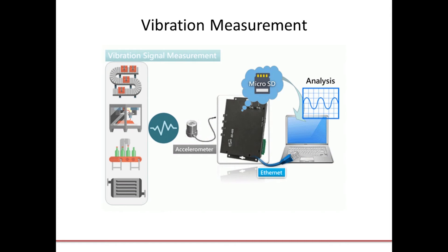The second component of our predictive maintenance system is the system which measures vibration. Vibration in a system, process, or machine is monitored and used to detect anomalies and avoid failures. Vibration analysis is commonly used for rotating machine faults such as unbalance, misalignment, looseness, loose bearings, and resonance. These conditions can be detected by vibration analysis. In this case, we're using an accelerometer to measure vibration and collecting the data with one of our accelerometer data loggers.